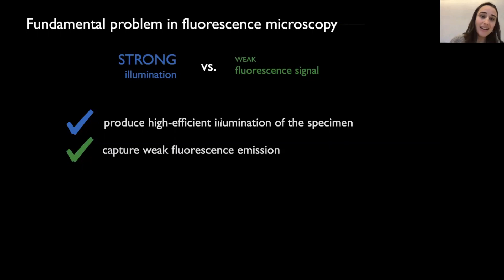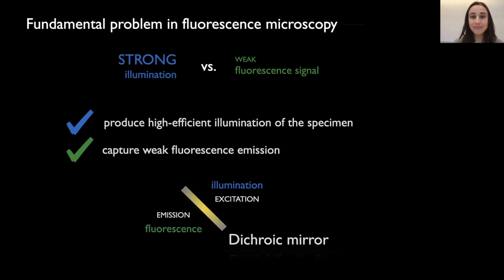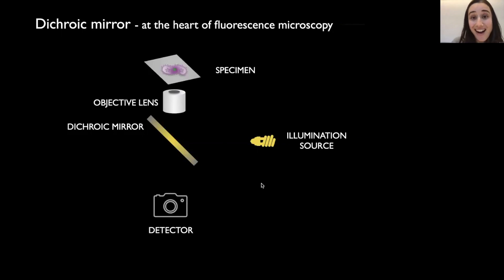And so how do we solve this problem? Well, we want to produce a high efficient illumination of the specimen as good as possible to try to increase the chances of this process to occur. And at the same time, capture the weak fluorescence emission coming from our probes. And we can only do that if we indeed separate the two light paths, the illumination or excitation light path from the fluorescence, which is the emission light path. And that is done with a dichroic mirror. So the dichroic mirror is really important because it's the one that separates its two light paths. And that is done because the dichroic mirror has several coatings, special optical coatings that will be reflecting some wavelengths and letting pass through other wavelengths. And this happens with the interference like destructive or constructive interference. So that's why the dichroic mirror is at the heart of fluorescence microscopy.